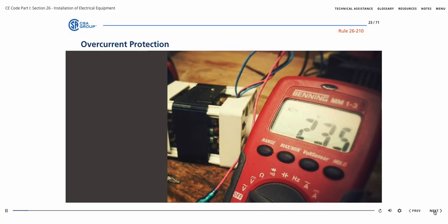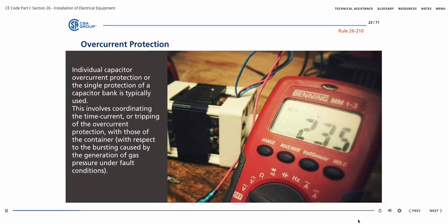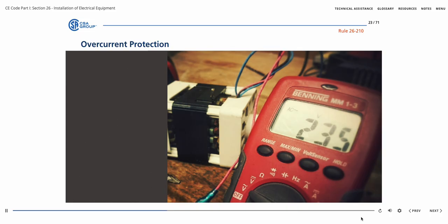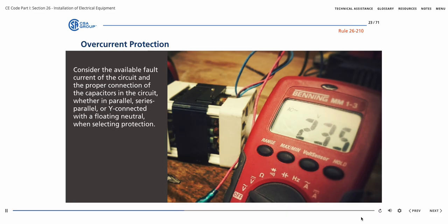It is essential to address overcurrent protection factors and to protect capacitors against bursting if a unit becomes defective. Individual capacitor overcurrent protection or the single protection of a capacitor bank is typically used. This involves coordinating the time current or tripping the overcurrent protection with those of the container, with respect to the bursting caused by the generation of gas pressure under fault conditions. It is necessary to consider the available fault current of the circuit and the proper connection of the capacitors in the circuit, whether in parallel, series parallel, or Y-connected with a floating neutral, when selecting protection. Improper capacitor connections can also cause overvoltage on adjacent units upon failure of a unit.